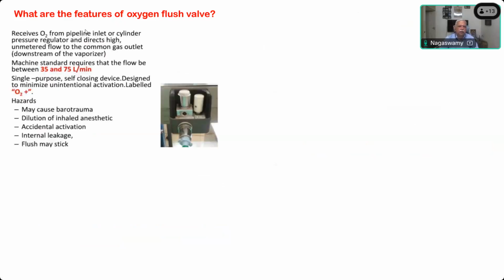It delivers 100% oxygen, 30 to 60 liters per minute, at intermediate pressure level. Peak flow rate, at high pressure values. High pressure, correct. But how many liters will it deliver if you activate it? 35 to 75 liters per minute. Very good. So this is oxygen from the pipeline inlet or cylinder pressure regulator, and it directs high unmetered flow to the common gas outlet downstream of the vaporizer. The machine standard requires that the flow be between 35 to 75 liters per minute.